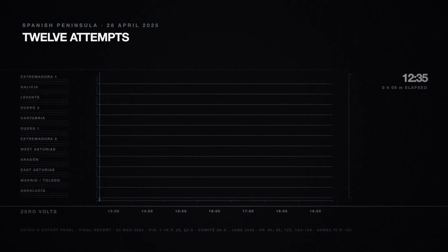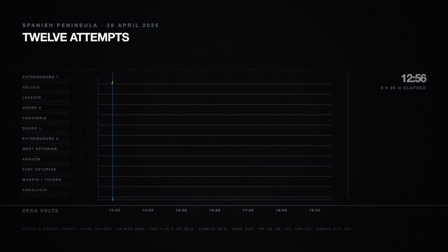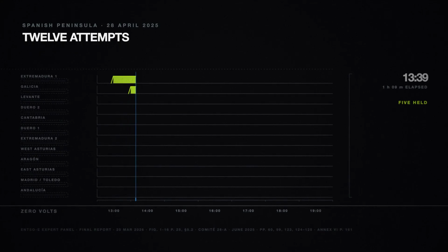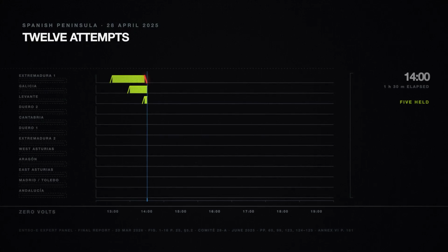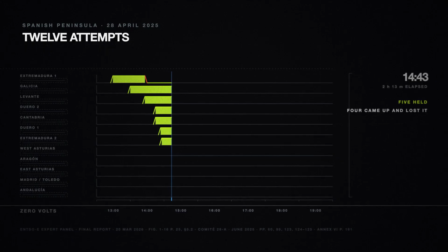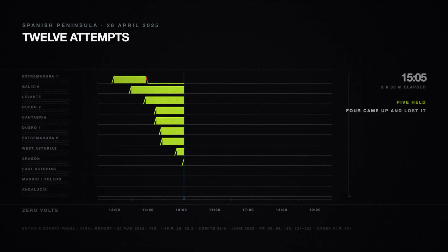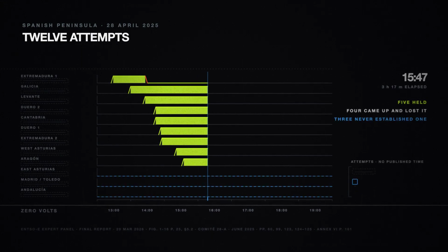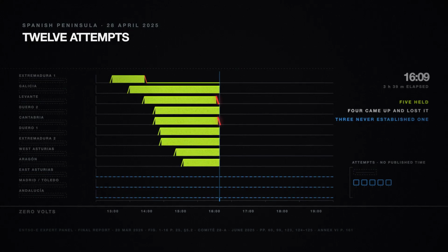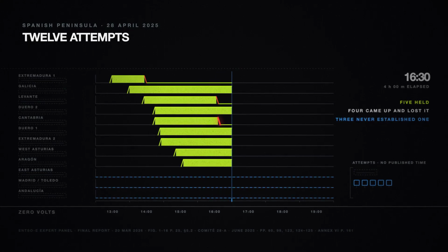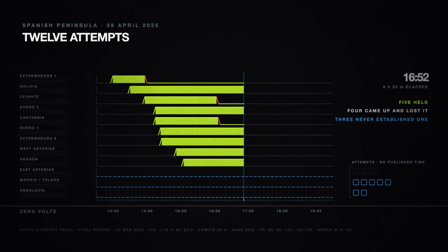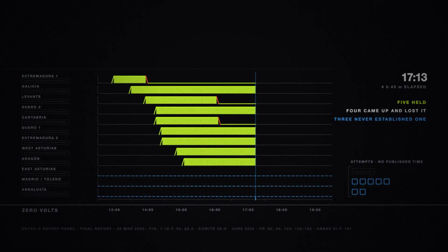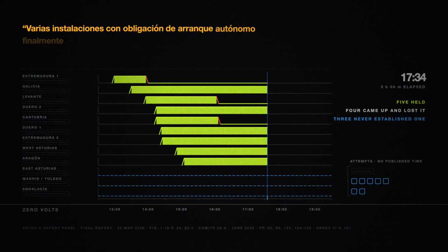There were 12 black start attempts in Spain that afternoon. 5 held, the first island up at 11 minutes past 2, the last at 1 minute past 3. 4 came up and then lost it, the last holding until 16 minutes past 7 that evening. And 3 never established one. The Madrid and Toledo area tried 5 successive times and failed 5 times. Andalusia failed twice.